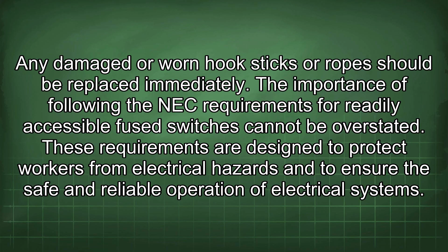To reiterate, the National Electrical Code, specifically Section 404.8, mandates readily accessible fuse switches for inspection and fuse replacement. When fuse switches are positioned at elevated locations, such as 15 feet above the working surface on a busway installation, it becomes imperative to have a dedicated hook, stick, or rope readily available for each switch.